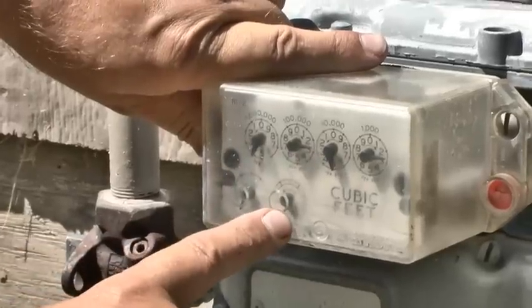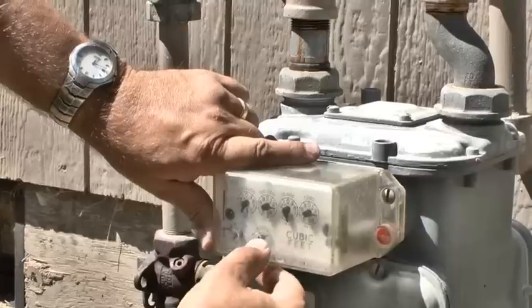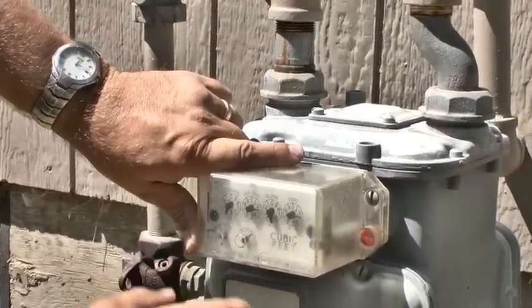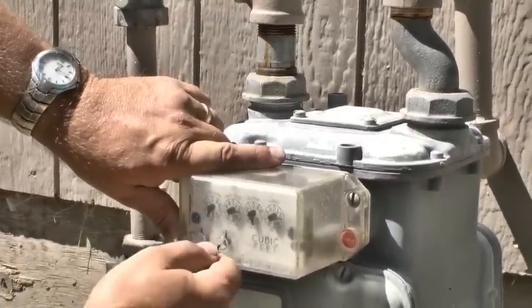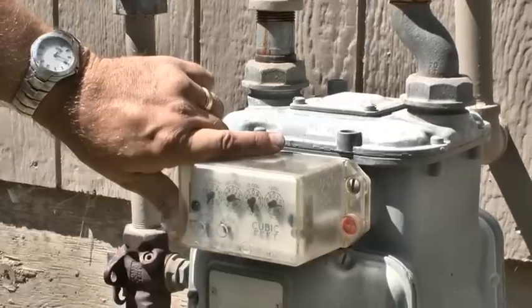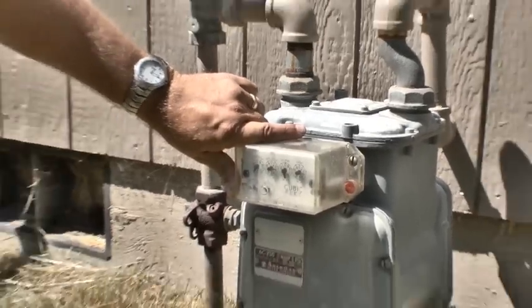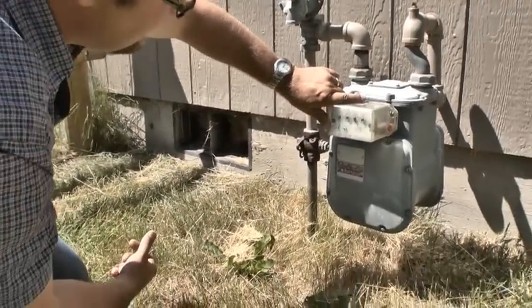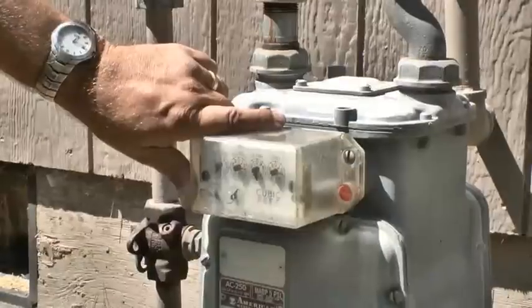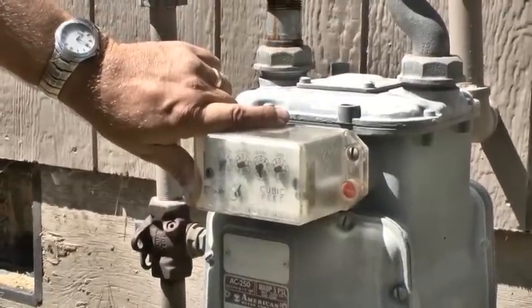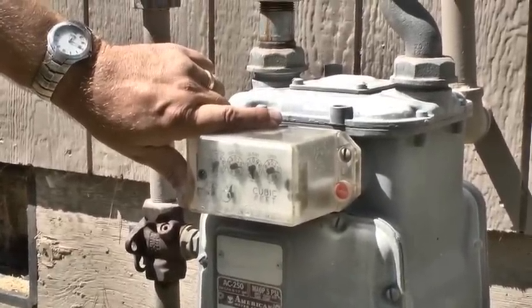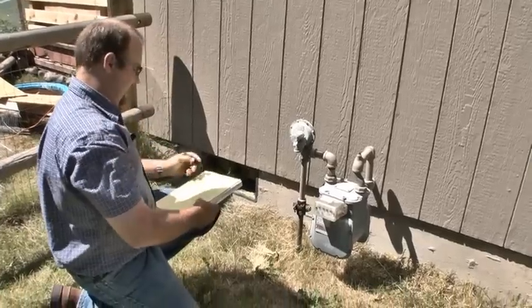Try to match it with my watch here. Okay, so I'm going to clock how many cubic feet of gas go through this meter. Started right here. The longer my measurement is, the more accurate I usually am. If I take real short measurements, my accuracy goes down. Okay, I had 1 cubic foot of gas go through this thing in 50 seconds. And then I do the math.